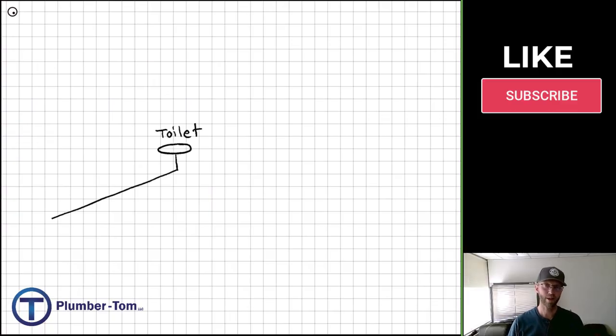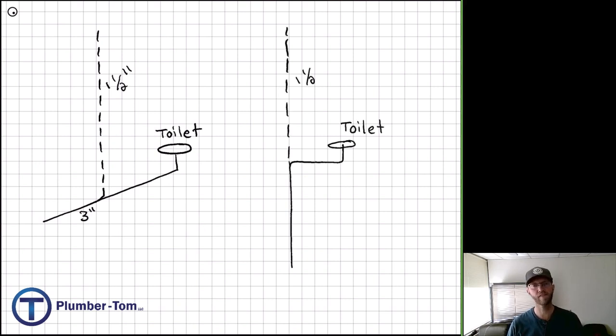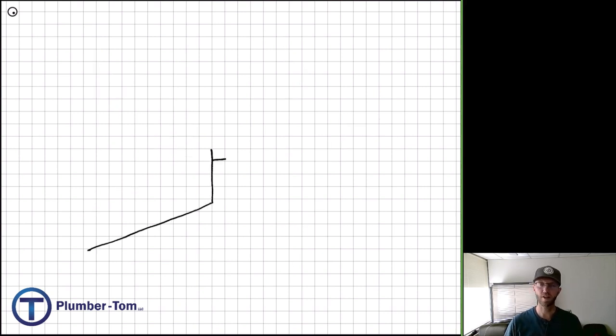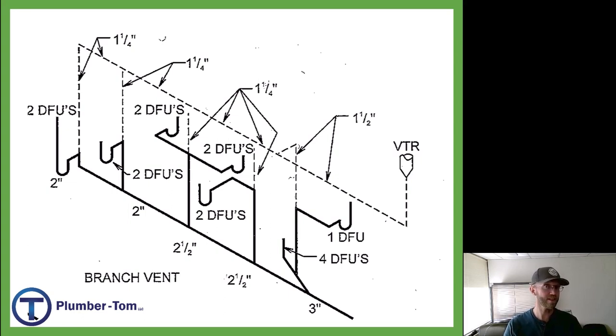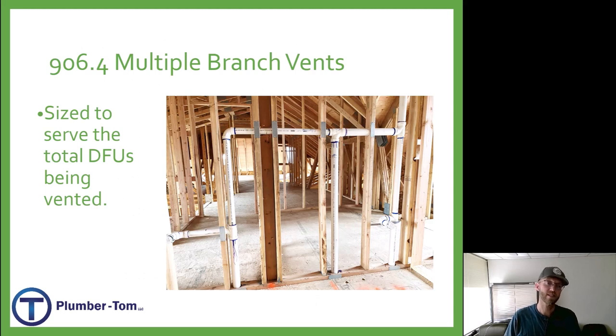Let's review what we know. For vent sizing, we have a minimum requirement of half the size of the drain pipe. Toilets on three inch pipes would each need one and a half inch vents. A lav could go with a smaller vent — as small as one and a quarter, but that's the minimum possible. We can get into branch venting where a bunch of drainage fixtures in a row have all their vents connected together. We'd look at each drain being served and the drainage fixture units — for most of these, one and a quarter or really one and a half inch is practical. Section 906.4 tells us that when we have multiple branch vents, the vent must be sized to serve the total drainage fixture units being vented.